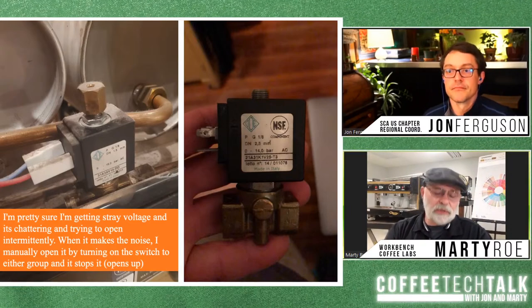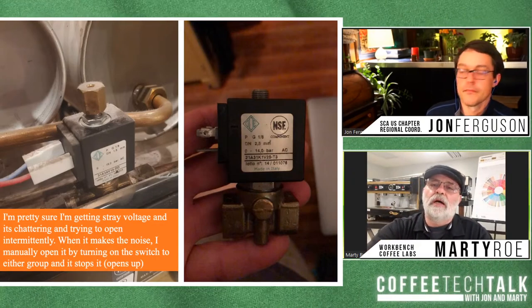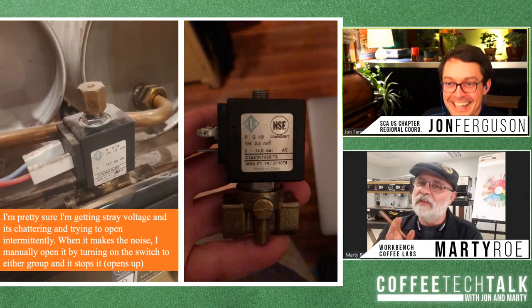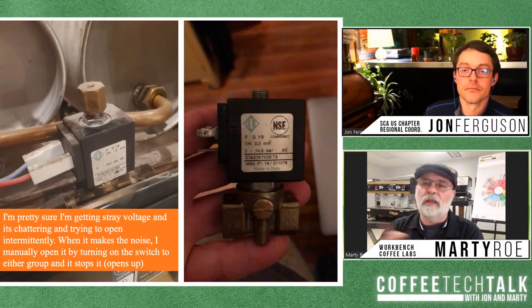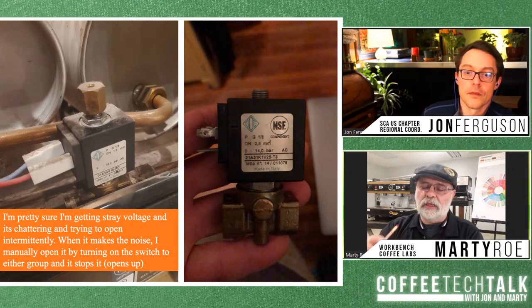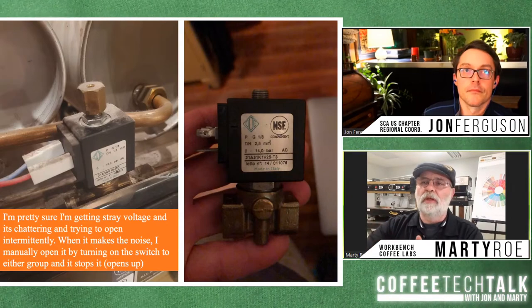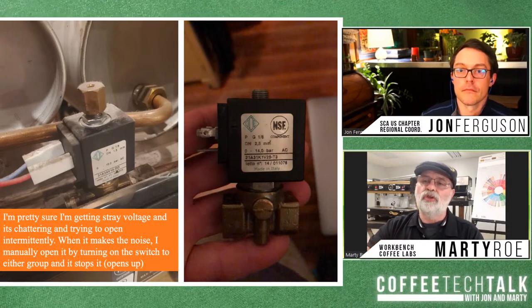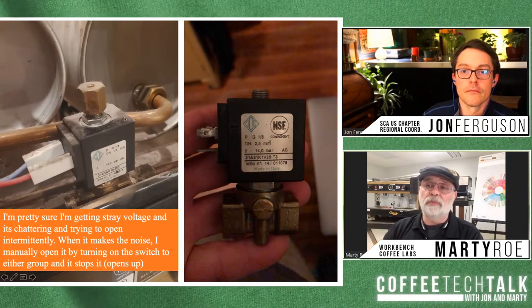Here's what we've discovered on this, and this can be cured. These valves are designed not in the coffee industry, but in the hydraulic industry, to have an input and an output. If it's installed correctly, the pressure side, or the input side, helps the plunger seat. So the more pressure, the more the plunger wants to seat. Whereas if you put it in backwards, you could exceed pressure enough to lift the plunger up off and it leaks by. And we don't want it leaking by on a machine and flooding the boiler.